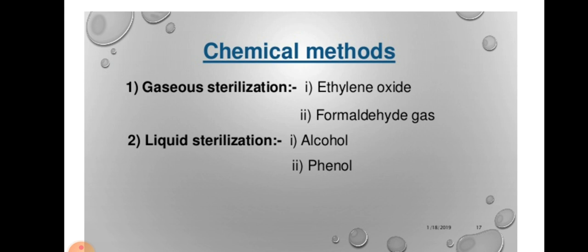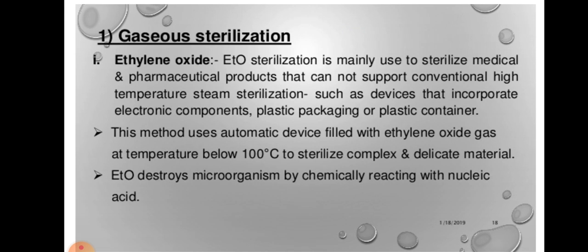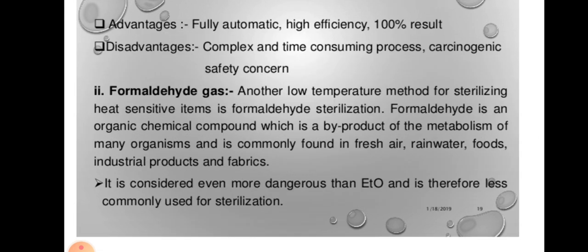Ethylene oxide sterilization is mainly used to sterilize medical and pharmaceutical products that cannot support conventional high temperature steam sterilization, such as devices that incorporate electronic components, plastic packaging or plastic containers. This method uses an automatic device filled with ethylene oxide gas at temperature below 100 degrees centigrade to sterilize complex and delicate materials. Ethylene oxide destroys microorganisms by chemically reacting with nucleic acids. Advantages: it is fully automated, highly efficient, 100% result is obtained. Disadvantages: it is a complex and time-consuming process and is also carcinogenic.